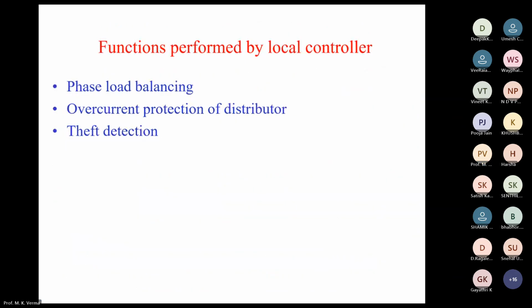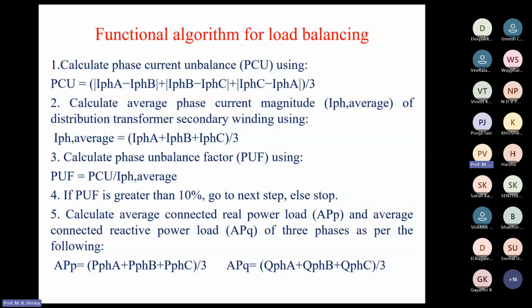The functions performed by the local controller were phase load balancing, overcurrent protection of the distributor, and theft detection. For phase load balancing, he developed an algorithm that calculated the average of the current differences between different lines and also the average of the three currents. Based on that, he calculated a ratio, the phase current unbalance divided by the average current. If this phase unbalancing factor is greater than 10%, then he suggested shifting load from one phase to another phase to achieve load balancing.